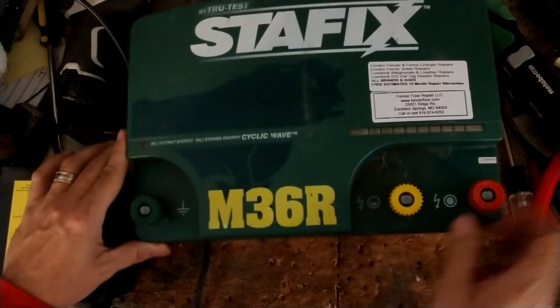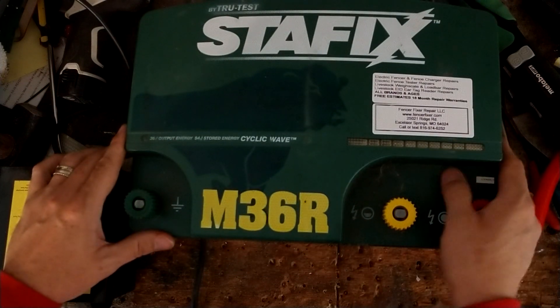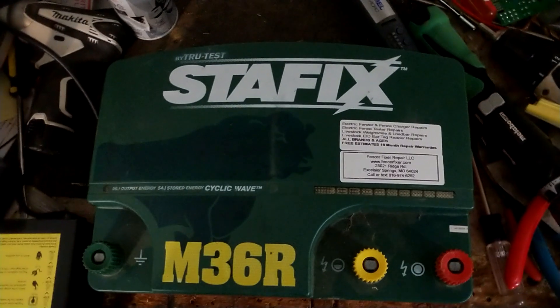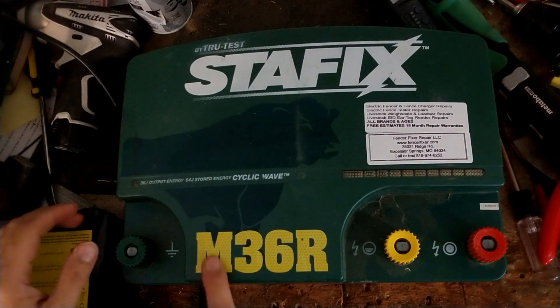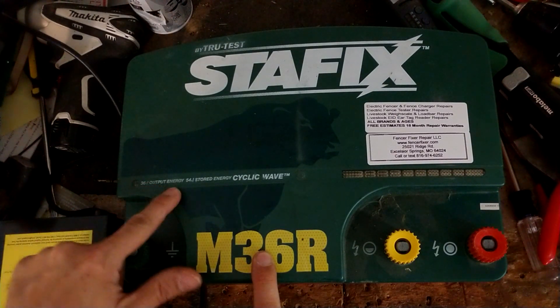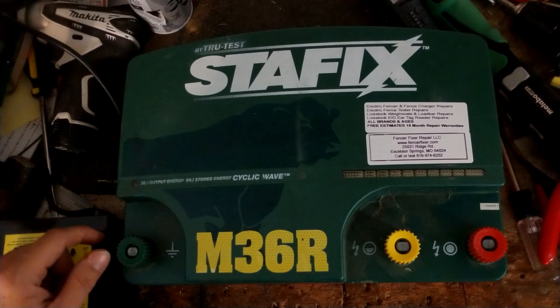It's a pretty good-sized unit. This is a Stafix M36R. If you look down here, the 36 refers to 36 output joules, or output energy, with 54 joules stored. So it packs a pretty good wallop. This is a pretty stout unit. I believe M stands for mains, which means AC plug-in power, and 36 is related to the output energy in joules. R stands for remote.